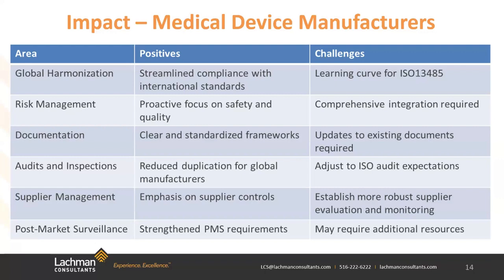The requirements for post-market surveillance have been strengthened, which will improve the ability to detect and address issues, leading to safer devices. However, for those manufacturers that do not already have a strong post-market surveillance program, this will require them to improve the monitoring, reporting, and corrective actions by updating their processes and procedures. Those are just some of the impacts, both positive and challenging, that I see facing some of our medical device manufacturers.